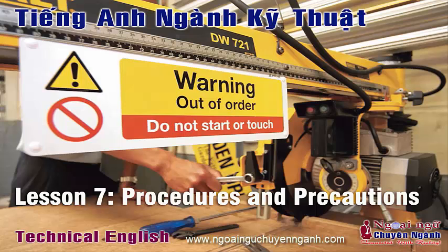Whatever happens, someone cannot switch on a circuit at a switchboard while somebody else is working on it elsewhere in the plant. If a technician needs to change a motor on one of the lines, they get a permit to work and obtain the key to the switchboard from the electrical supervisor. Then they take the key, unlock the door to the switchboard, switch off the circuit breaker for the motor to isolate it, then lock the door again.